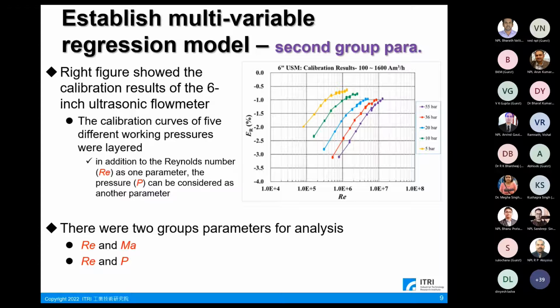In the second place, we consider another method to determine the parameters. This figure showed the calibration results of the 6-inch ultrasonic flow meter. The calibration curves of 5 different working pressures were layered. So, in addition to the Reynolds number as one parameter, the pressure can be considered as another parameter. Above all, there are two groups of parameters for analysis. One is Reynolds number and Mach number. Another is Reynolds number and pressure.